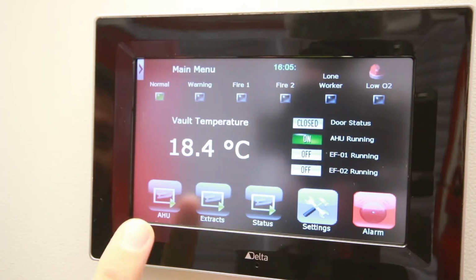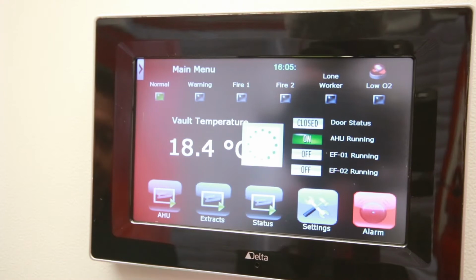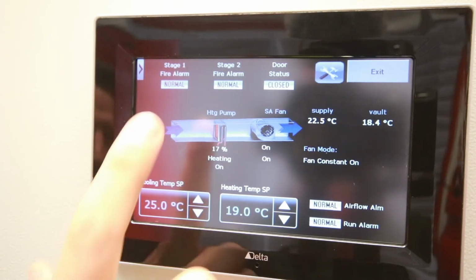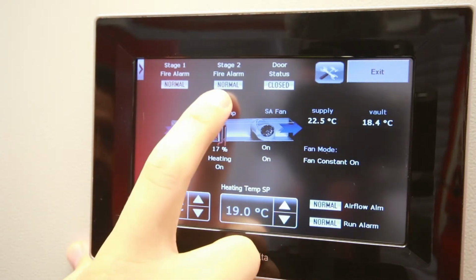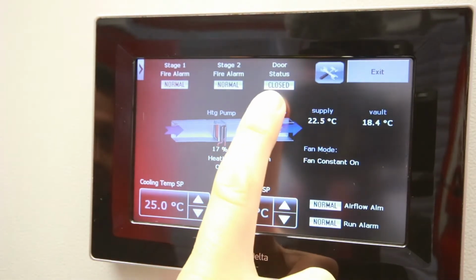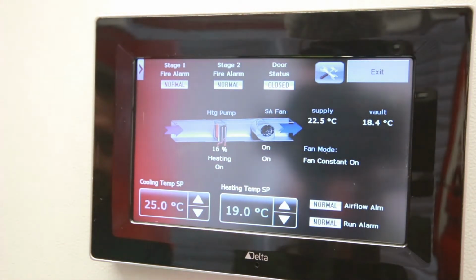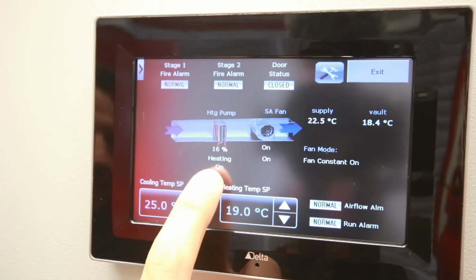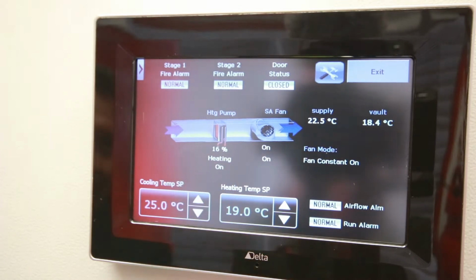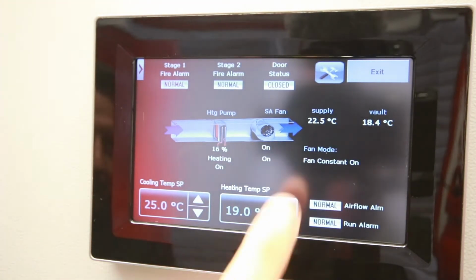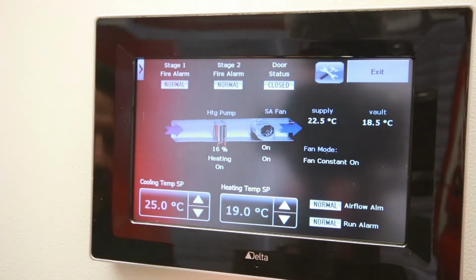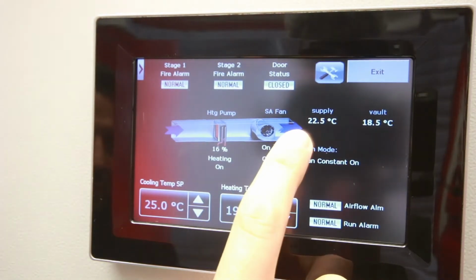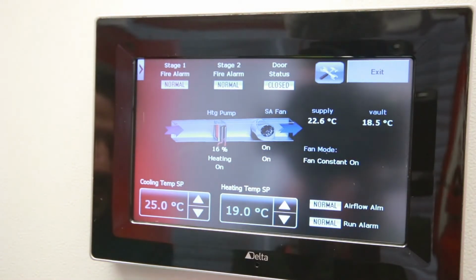So I'll take you through our main air handling unit control menu now. It's touch screen. Here we have a graphic showing the current running status in real time. At the top we can see our stage 1 and stage 2 fire alarms are normal. Again, our door interlock is closed, so everything is operating correctly. Here we have our return airflow to the air handling system running through the heater, which is currently running at only 16% to achieve our current internal temperature of 18.4. Our fan is operating correctly and is rotating, and our supply air back into the Firevault is at 22.6.